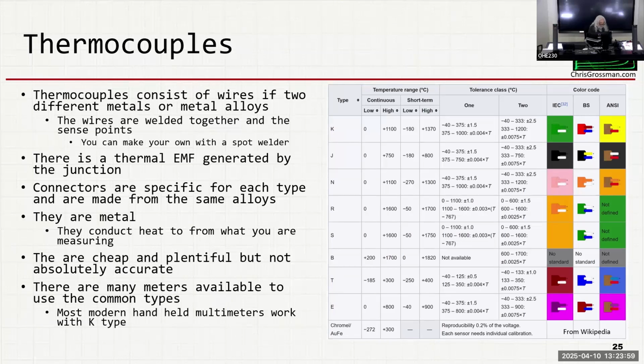There's a thermal EMF generated at the junction. There's a bunch of standard types of thermocouples, I have that in the table on the right. K is the most common. Multimeters like this one that measure temperature, we almost all use K thermocouples. There's connectors specifically for each type of thermocouple, where the connections are made of the same kind of metal that's in the wire, so you don't get thermal junctions in them, and they're color coded. That's why there's colors in the table on the right.